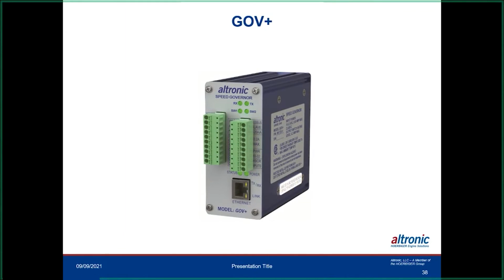Now, this one I'll add to the end here a little bit, then I'll turn it over to Curtis. This is a device that's been out for quite some time now, I'm guessing the last 5-6 years. It's a good add-on to the AGV5. It puts out a 4-20 to an actuator of some sort, and we have used them in the field a lot. It's a good way to control that valve if you decide to go with the AGV5 over the GOV10. It uses a lot of the same programming mechanisms that the GOV10 has in it.